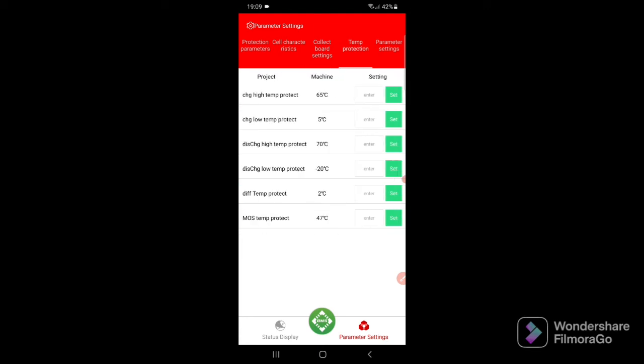Temperature protect is fairly self-explanatory, but we'll go through it. If the temperature of the battery, or the temperature probe, is above 65 degrees C, it won't charge. If it's below 5 degrees C, it won't charge. You should never charge LiFePO4 batteries below 5C.